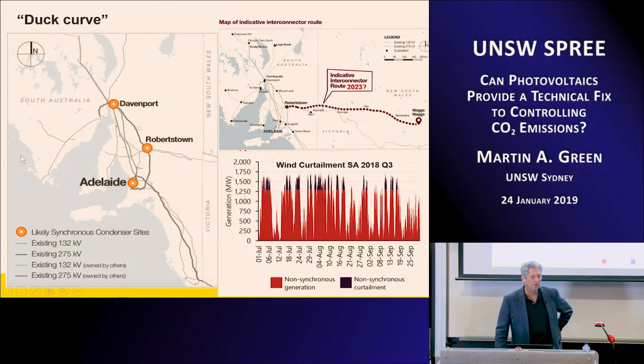The other thing you can do is add what are called synchronous condensers to the grid network. This is what they're also planning to do - stick some of them in critical parts of the grid. What these really are is a pretty traditional generator, but just not connected to any load. It's just there, spinning around, providing that inertia that the grid needs.